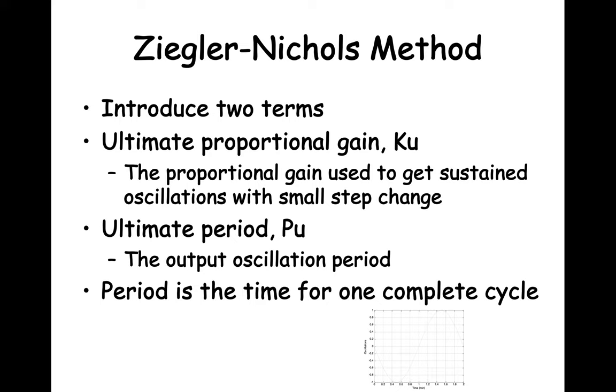When using the Ziegler-Nichols method, we are looking for the ultimate proportional gain Ku and the ultimate period Pu. The ultimate proportional gain is the gain setting used to produce the sustained cyclic process output after the process is subjected to a small step change. The ultimate period Pu is the period of the oscillating process output. Please remember that the period is the time for one complete cycle.